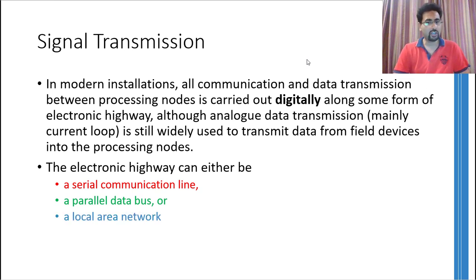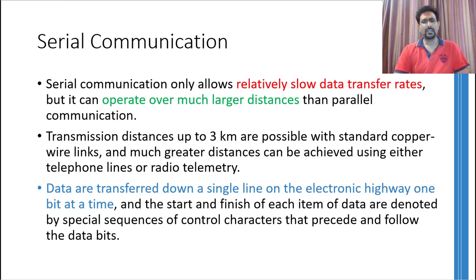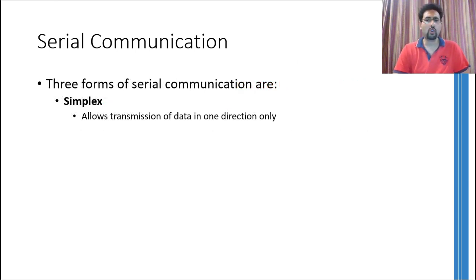A local area network can utilize serial communication or parallel buses. You can think of the local area network as a large network of roads in which some roads are multi-lane, whereas others are single-lane. Serial communication has relatively slow data rates but can operate at much larger distances than parallel buses — you can easily achieve communication distances of up to three kilometers using simple copper wire links. For higher distances, telephone lines, radio telemetry, and sometimes fiber optics are used. In serial communication, only one line is used to transfer data, so in its most basic form only one bit at a time is transferred. Start bits and end bits are used to notify the receiver about the start and end of data.